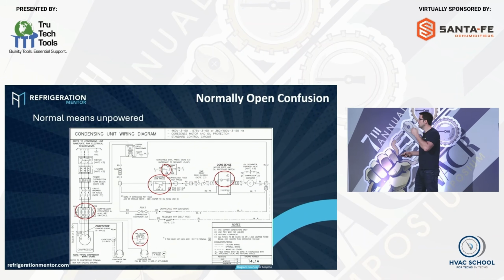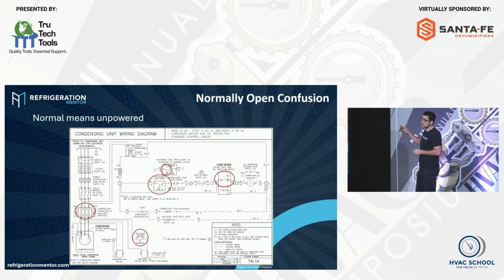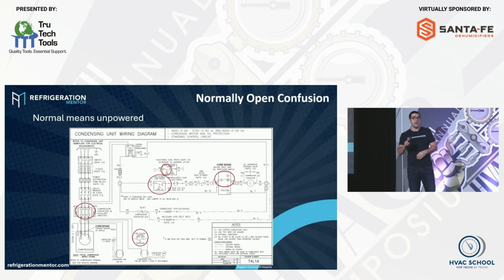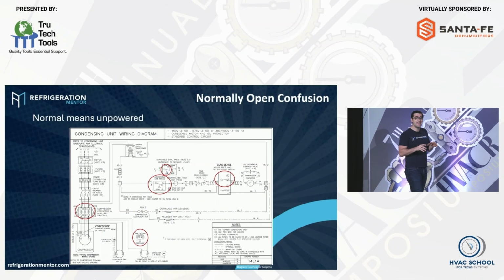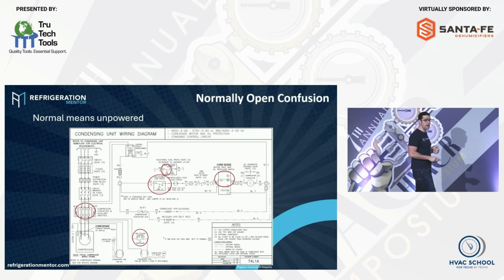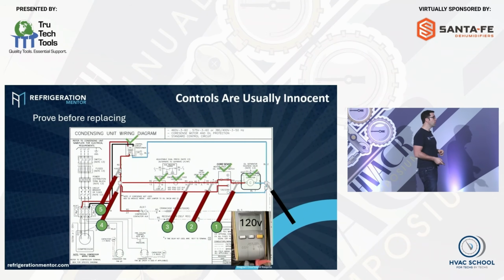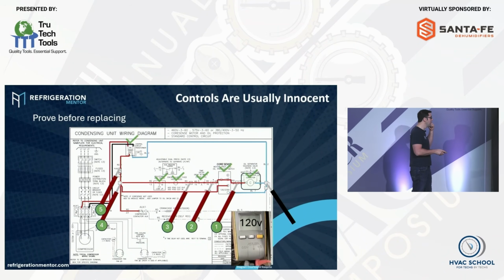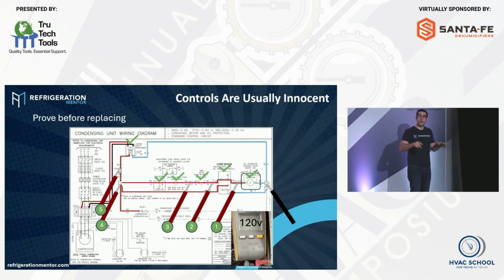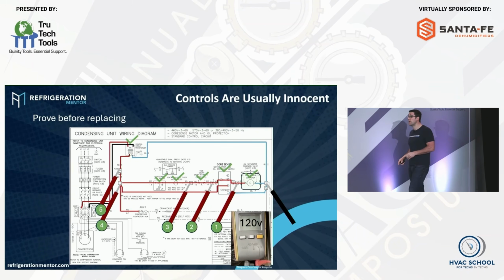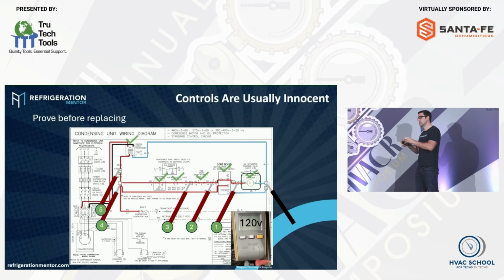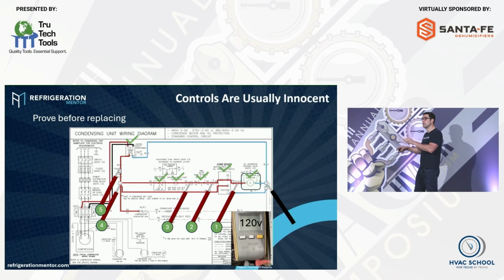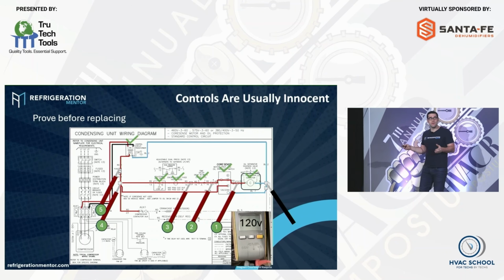That is normally open confusion, okay? What does that really mean? Normal means unpowered. Like I said earlier, this diagram, and every diagram you look at, is de-energized, okay? That means unpowered when you first look at it. Controls are usually innocent. Prove before replacing. So many parts. Right now, out there in the field, somebody's changing parts that they're not proving. They're like, okay, let's pull it out and just try it. Does it work? No. Okay, let's try another one. Let's put the motor in and change it. Just prove it. Your meter is not going to lie to you if you use it properly.